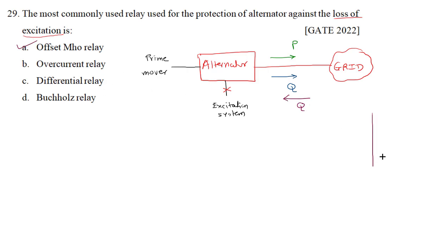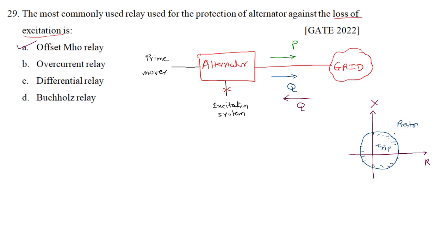The correct answer is option A. Now, how does the offset mho relay characteristic look? On the R-X plane, a normal mho relay passes through the origin, but the offset mho relay gets shifted either downward or upward. Within this characteristic the relay trips; outside it, the relay rests. So for loss of excitation, we use the offset mho relay.